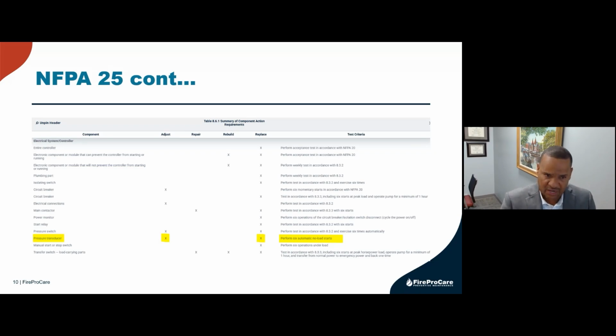So if you change that transducer, the key point here is that you have to perform 6 automatic starts. Is that happening? Those are the types of questions I always have when I started working on this part of the business, when I moved from working on the controller side directly. I learned that is not happening, and that is a concern. If you go to change something in that control panel, whether it fails or whether it's preventive maintenance, there are guidelines on what you should do, and you should be working with the manufacturer as well for their recommendations on how to do it. I seriously doubt that a lot of people are starting and stopping that panel 6 times when they change the transducer. So very concerning, but my goal here is to educate you and get you more information.